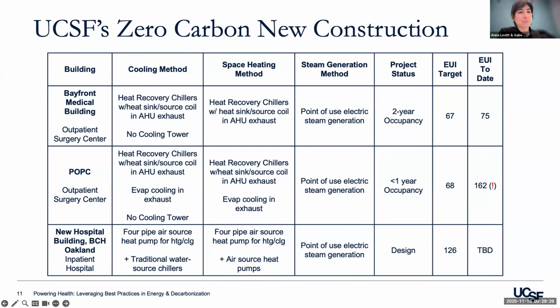The design is based around heat recovery chillers, with each building having what we call a heat sink source coil in the exhaust airstream of the main air handlers. When heating and cooling aren't balanced, that coil can reject heat by running heating hot water through it into the exhaust airstream, or absorb heat by running chilled water through it from the exhaust airstream.